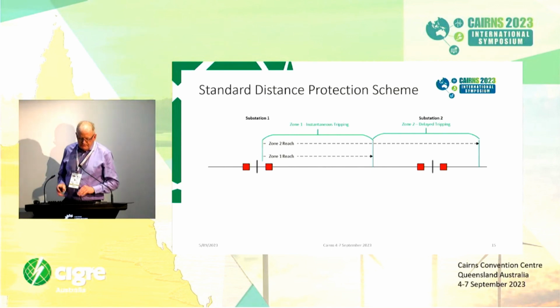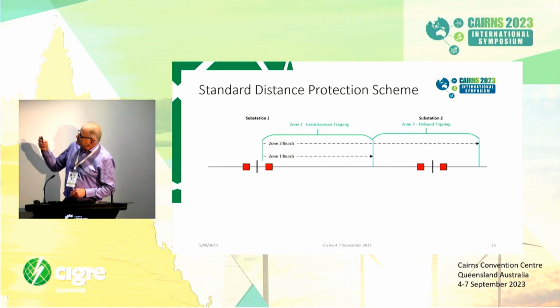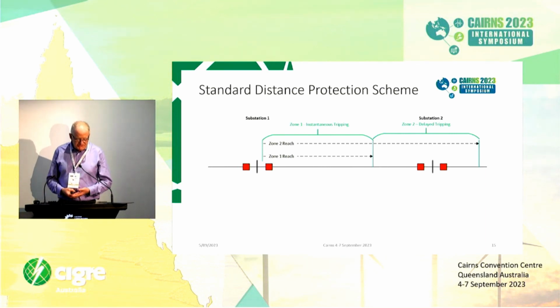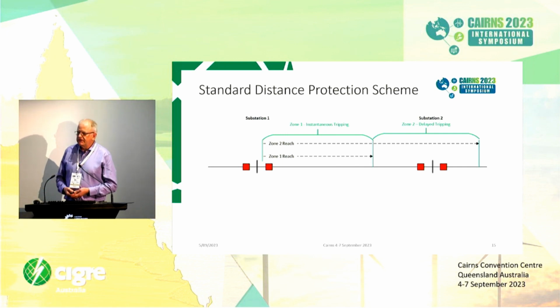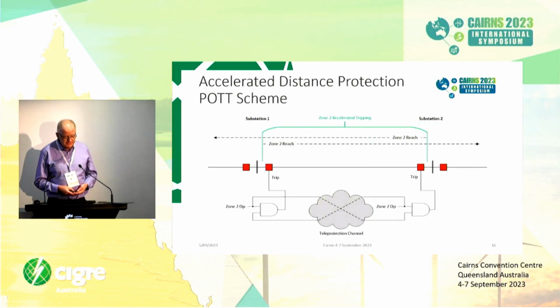So I'll just go through a high-level example of a couple of these schemes. First of all, distance protection. The way distance protection works, you have a zone 1 and a zone 2 and also a zone 3, but zone 1 reach typically protects the first two-thirds of a transmission line, and your zone 2 reach protects the entire transmission line plus into the adjoining segments. To make the protection coordination work, typically zone 1 will be on instantaneous tripping to trip in the fastest time on that line you're trying to protect, but then you've got to delay the zone 2 tripping to allow the protection on the adjacent circuits to trip in time and not trip. So from a protection perspective, we'd really like to trip instantaneously or as quickly as possible on the actual transmission line itself. That's where accelerated distance protection schemes come into play.